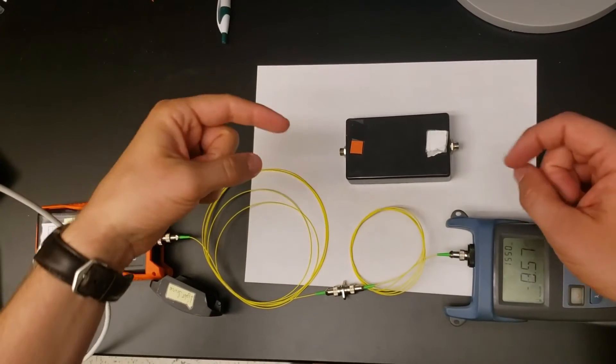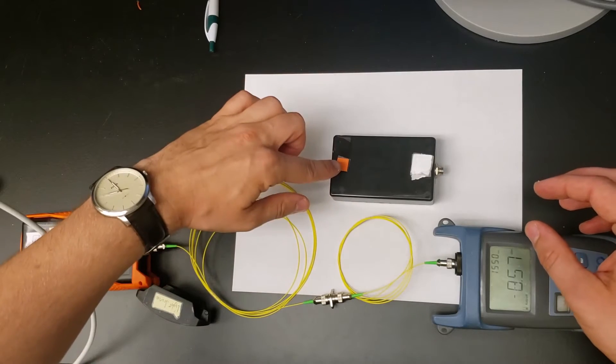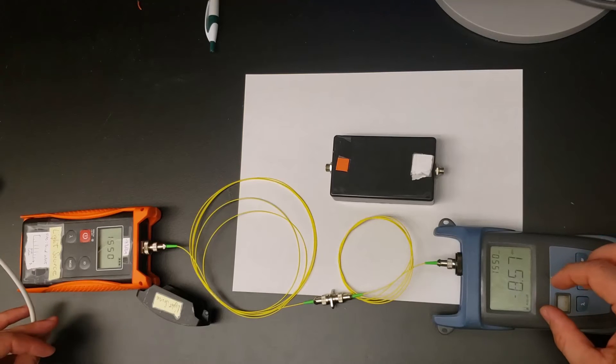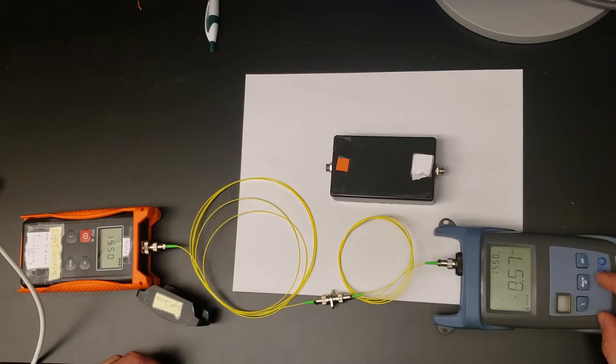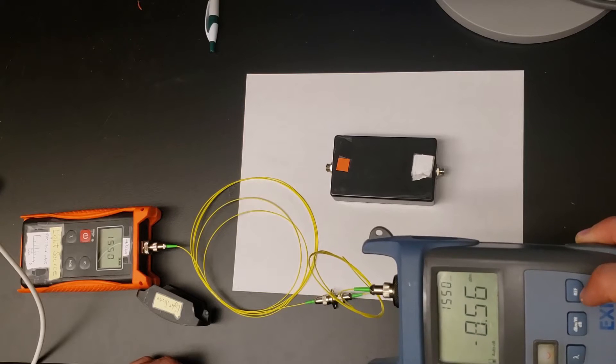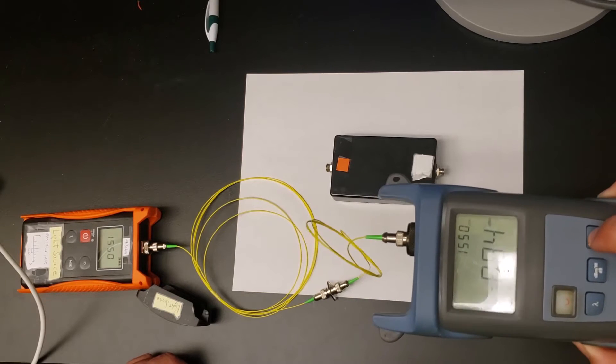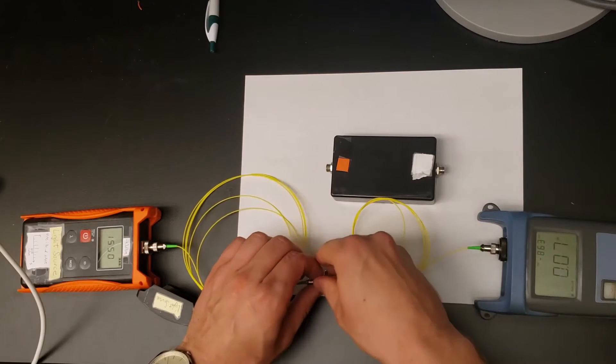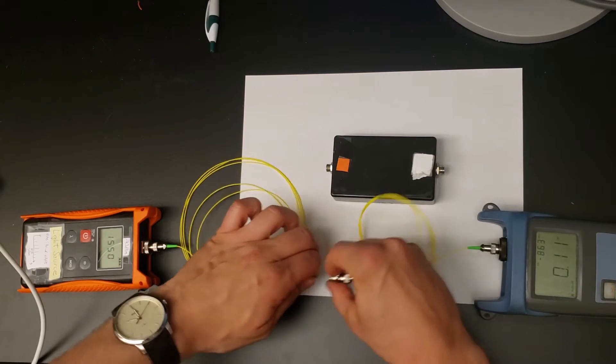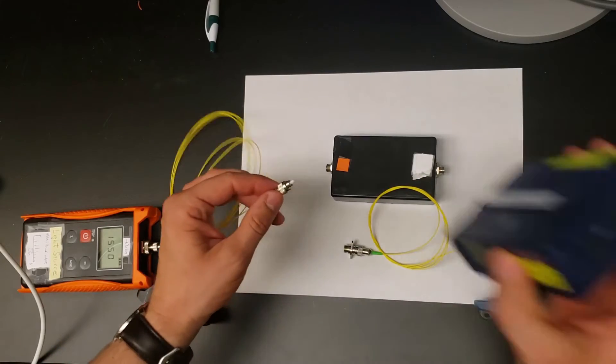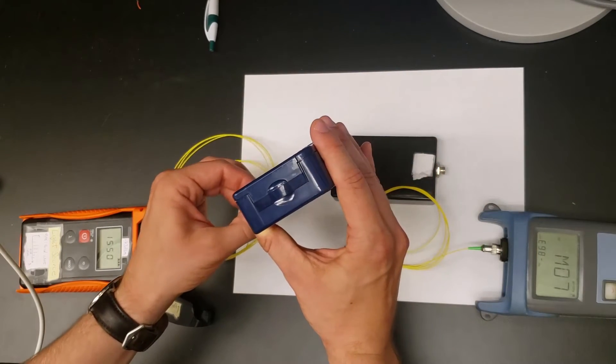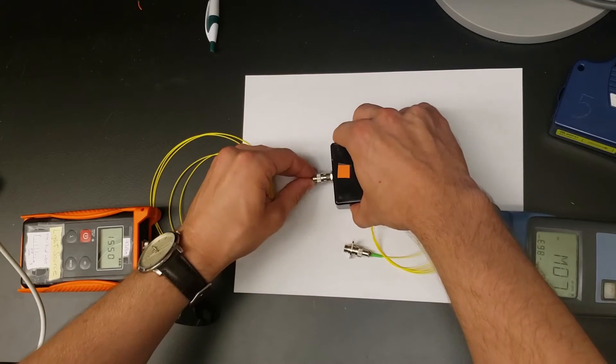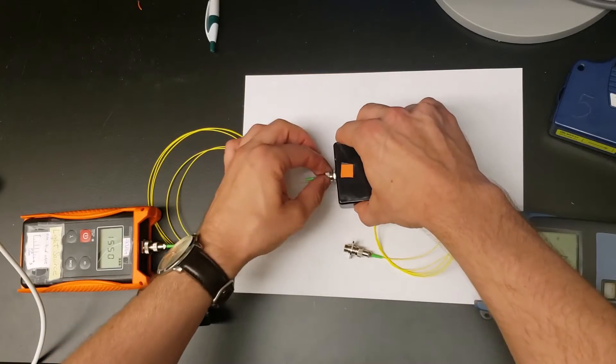Here we have another mystery device with two ports labeled orange and white. We also have a handheld laser and power meter. First I'm going to push this REF button which should normalize everything to the power coming in. Now I'll disconnect here and plug into the orange port, making sure I also clean it.